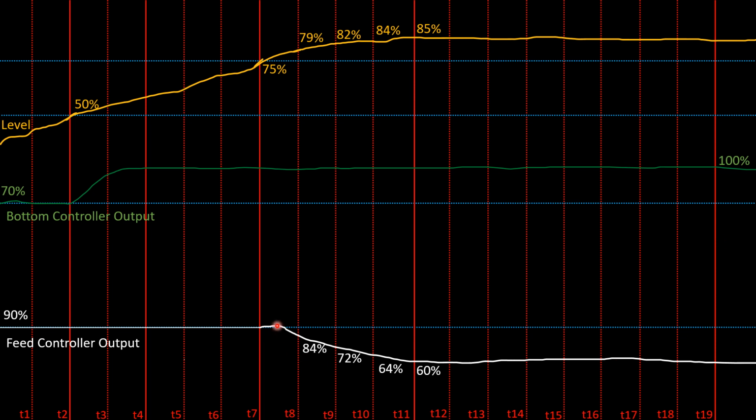So this example was a high override level controller for a base level distillation column. The typical manipulated variable, which is feed flow, was just to control the feed into the distillation column, but the base level was too high. With an abnormal condition, we want to protect the base level. We do not want to flood the column. Therefore, you have an override controller to control the feed rate in case the base level gets too high.